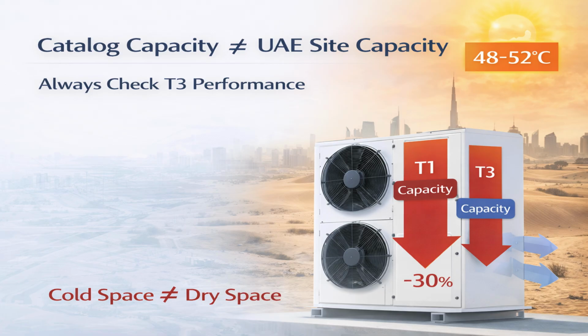T3 selection ensures that the unit can actually meet the design load during peak summer conditions, set points can be maintained without continuous operation, energy consumption remains predictable, and long-term reliability is not compromised due to constant overload. In simple terms, T1 tells us how the unit performs in ideal conditions, but T3 tells us how it performs in the real world. And in hot climate projects, it is T3 performance that determines whether a system succeeds or struggles.